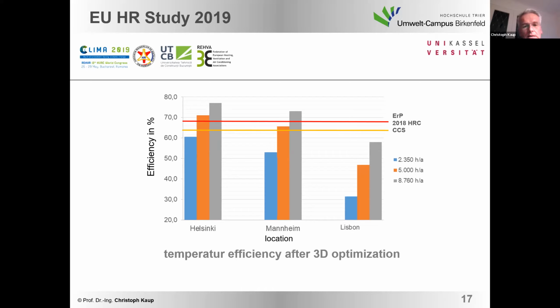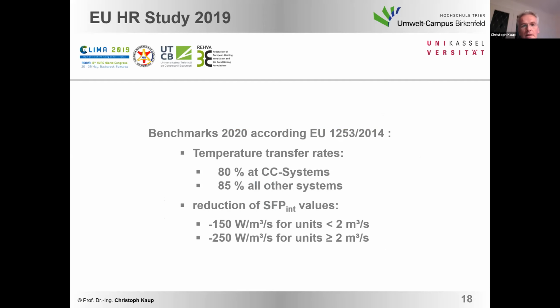So in the northern parts, a bigger heat recovery system makes sense, and in the southern part, for sure, in Lisbon, for example, if you have an office, it makes no sense to have more than 30% of efficiency, but that was calculated with the balance limit just on heat recovery, nothing else, no additional influence factors. But for hospitals, 60% also makes sense. In Helsinki, for example, heat recovery between 60 and 80% makes sense.